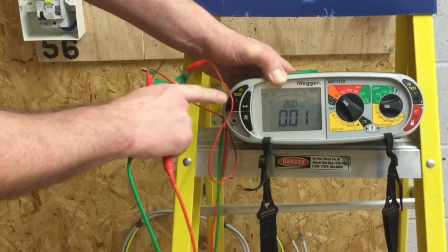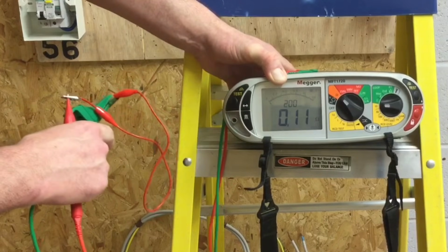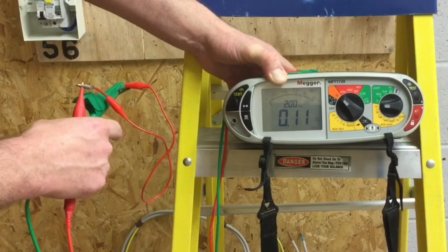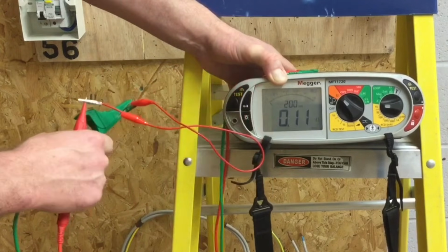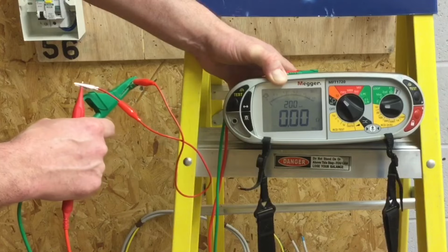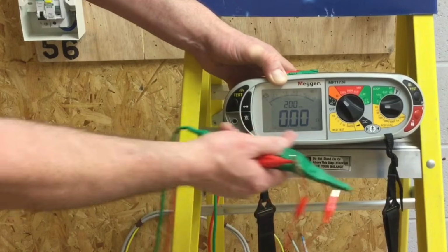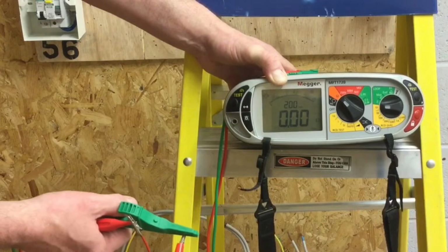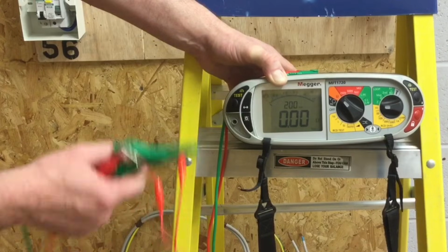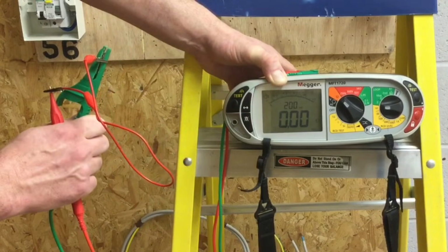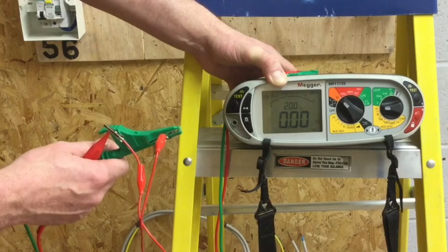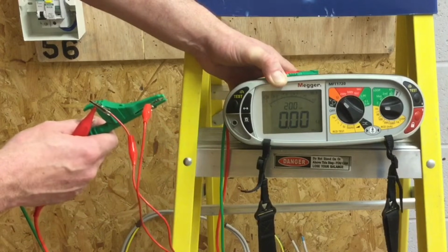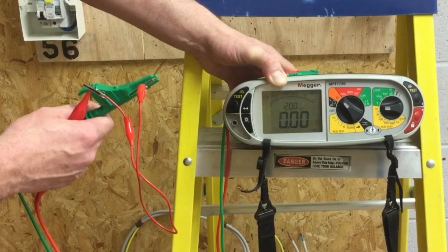You press the test button only once, and I've now got a reading, in this case, of 0.11, which isn't 0, so I need to press it just once again. And now I have 0. Be very careful with this instrument that it isn't 0 flashing. If the 0 is flashing, it is below 0 and would need the test button pressing at least once more. We have 0, we've removed the resistance of both the leads and the link, therefore we're ready to start the continuity of CPC and polarity test.